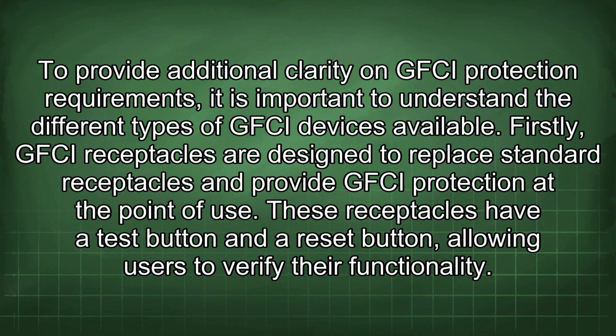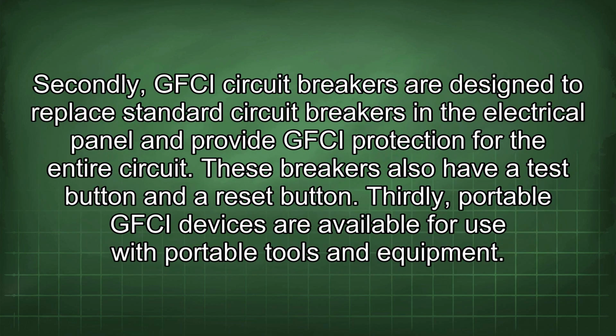Firstly, GFCI receptacles are designed to replace standard receptacles and provide GFCI protection at the point of use. These receptacles have a test button and a reset button, allowing users to verify their functionality. Secondly, GFCI circuit breakers are designed to replace standard circuit breakers in the electrical panel and provide GFCI protection for the entire circuit. These breakers also have a test button and a reset button. Thirdly, portable GFCI devices are available for use with portable tools and equipment. These devices plug into a standard receptacle and provide GFCI protection for the tool plugged into them.